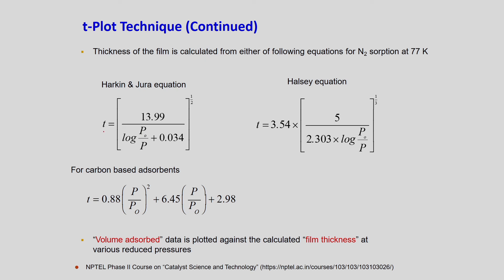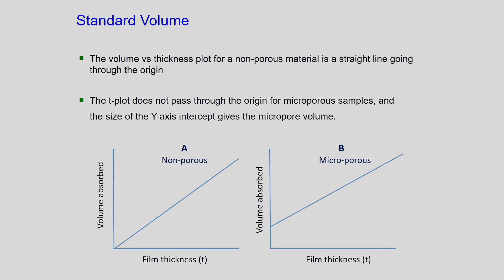For assessing statistical thickness, expressions available include the Harkins and Jura equation, the Halsey equation, and a correlation for carbon-based adsorbents. The volume adsorbed data from the BET instrument is plotted against film thickness rather than partial pressure, using these expressions. For a non-porous material, the volume versus thickness plot is a straight line through the origin.